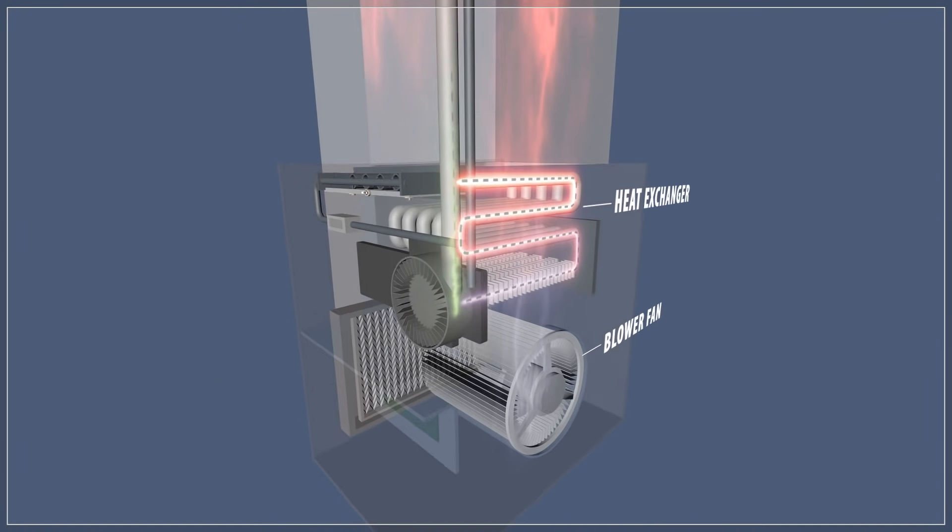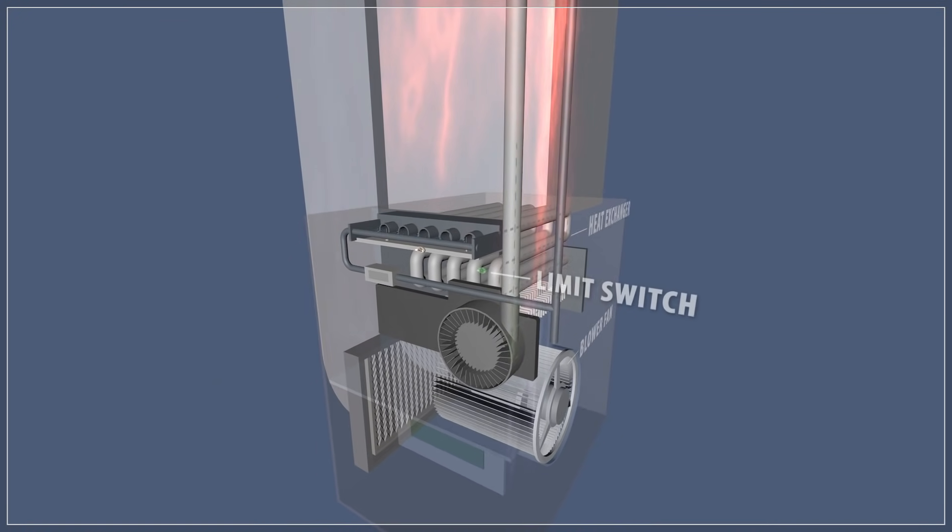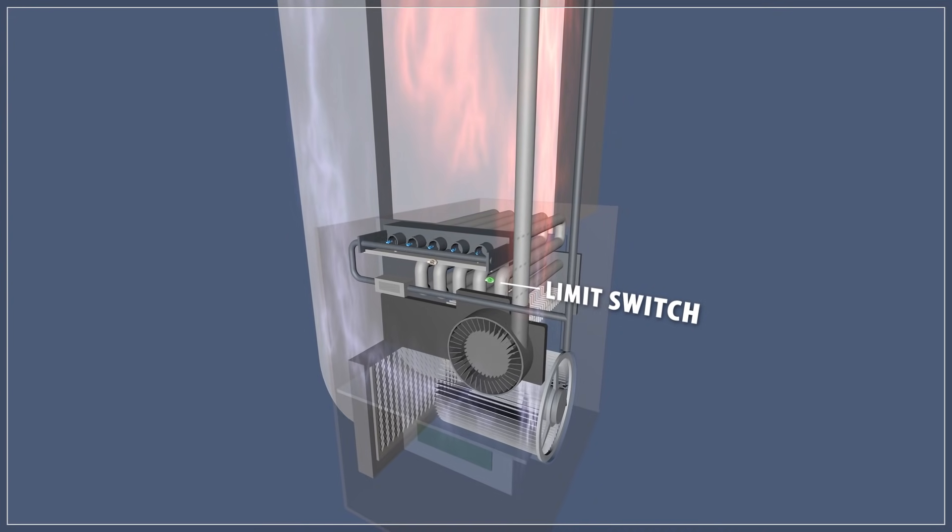Now even if a limit switch has continuity, it doesn't always mean that it's functioning correctly. Sometimes limit switches can start cutting out early and might prematurely shut down the furnace.